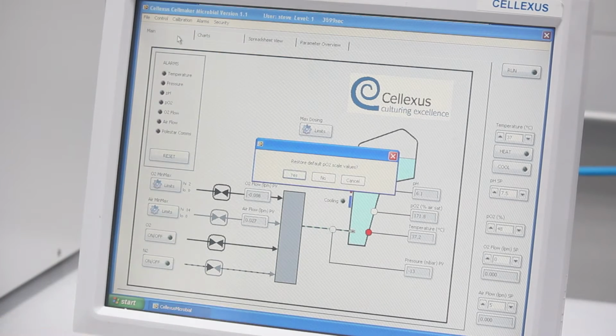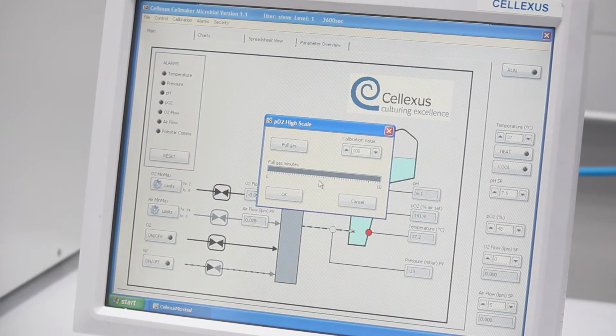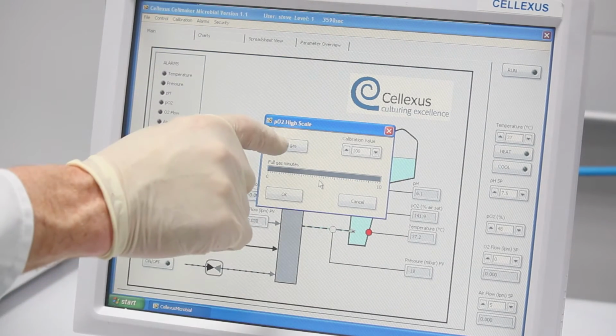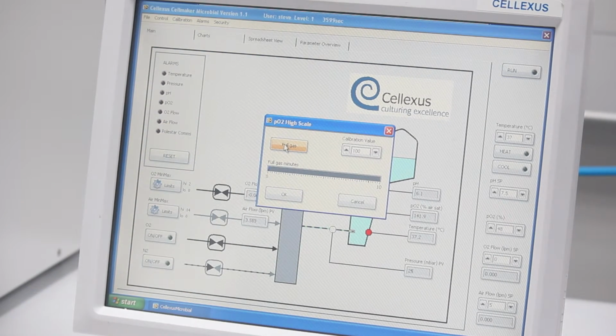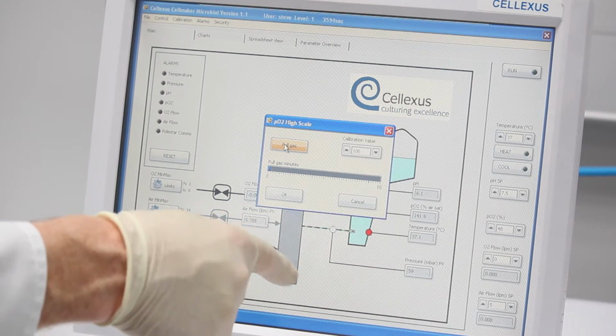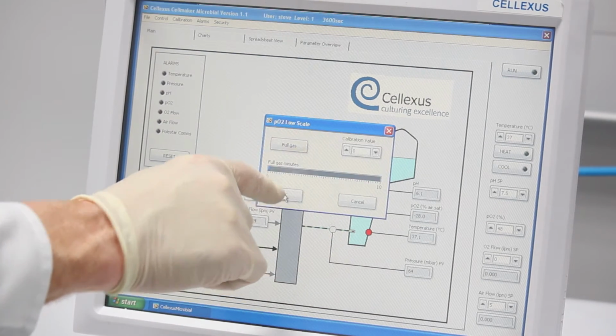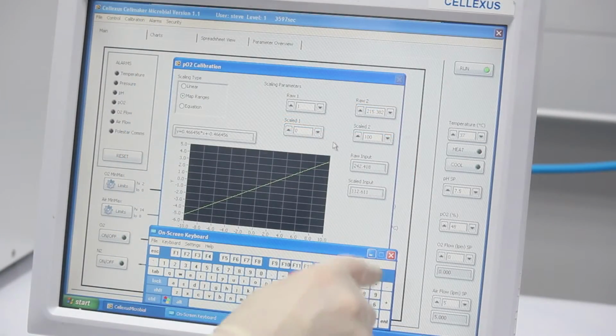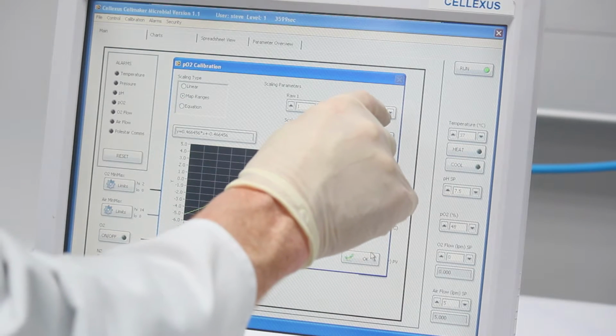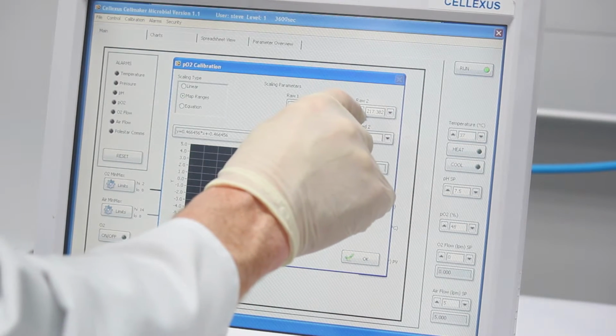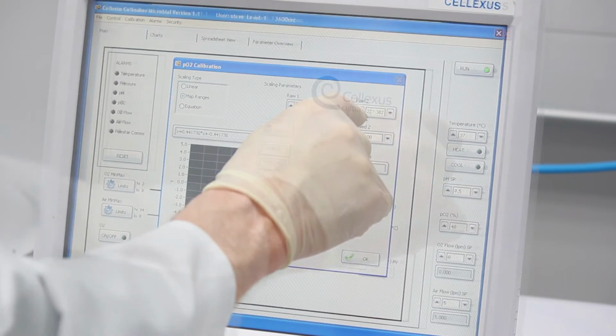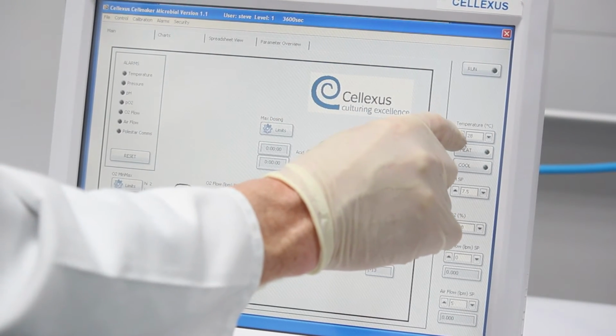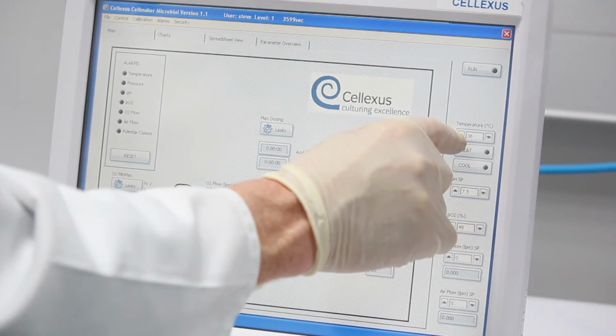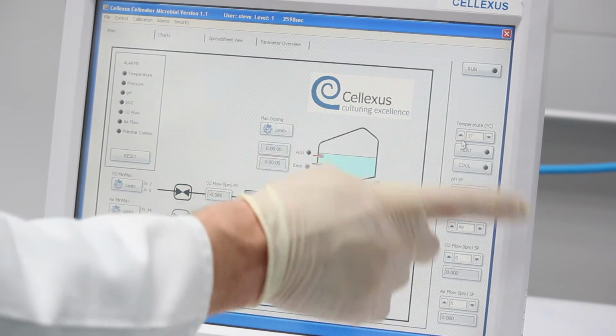To ensure the temperature probe is stabilised, and in the case of the Cellmaker Plus, that the sensors are suitably hydrated, a stabilisation step of approximately 30 minutes is performed. A dissolved oxygen calibration cycle, which takes approximately 20 minutes, is then conducted. The temperature is now set via the touchscreen and adjusted by the scroll keys.